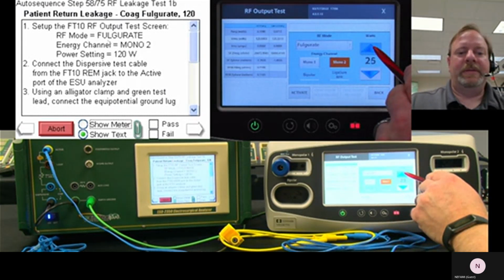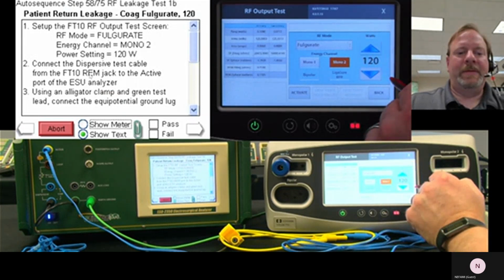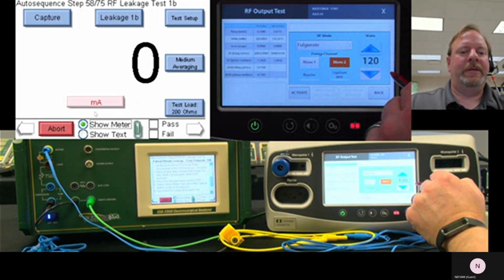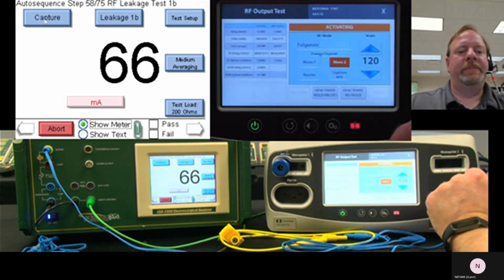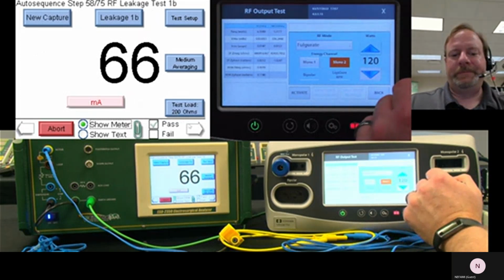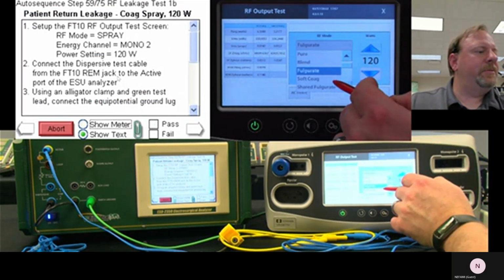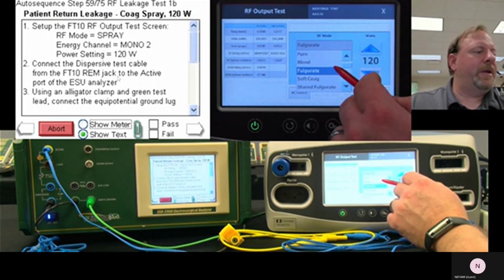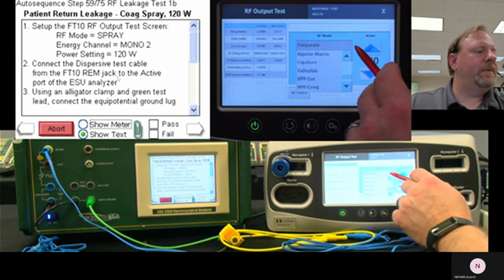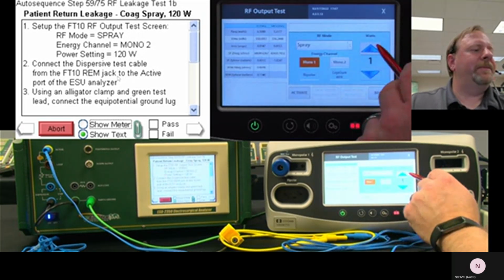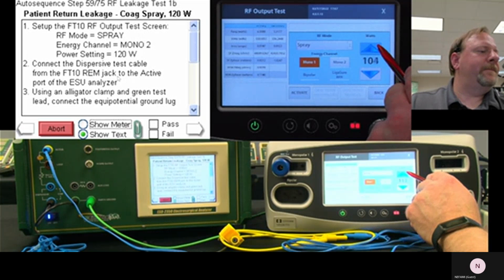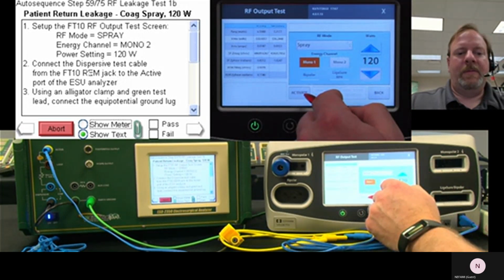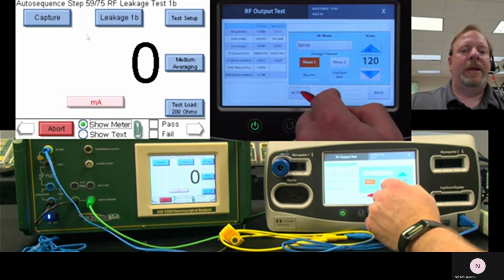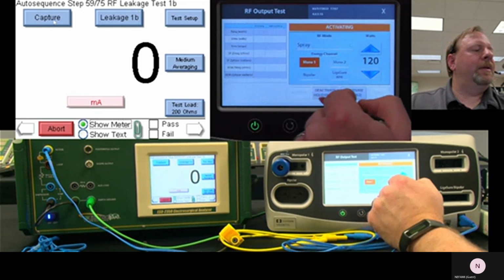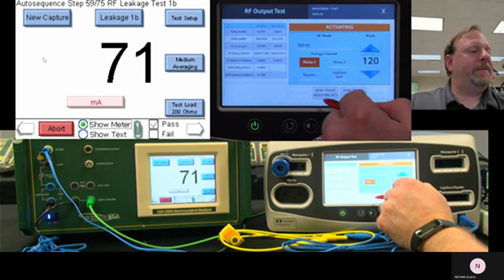Fulgurate, 120 watts. Dispersive is still connected. Ground is still connected. That was a little higher. Mono 2 spray. Come on. Spray. Max power. Still going through the REM port. And this is the other indicator, leakage 1B. Tells you we're going through the REM capture.